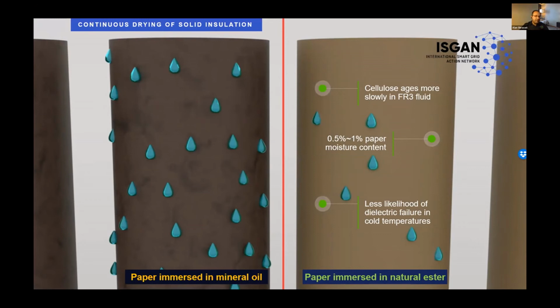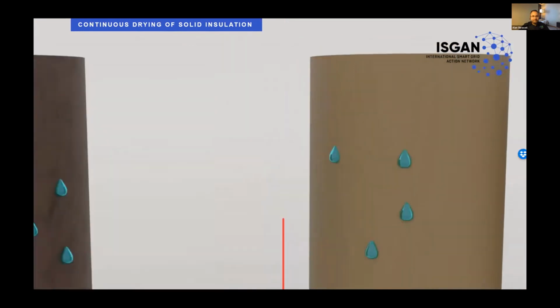So the result is what you see here on the screen. The comparison that you saw is exactly this. When you reach end of life for the paper immersed in mineral oil, you have only consumed 16% of the useful life for the paper immersed in a natural ester. And on top of that, the paper is drier. And a drier insulating system is a better dielectric. So you don't compromise the reliability of your transformer after years of operation. If you could move to the next, Fernando.